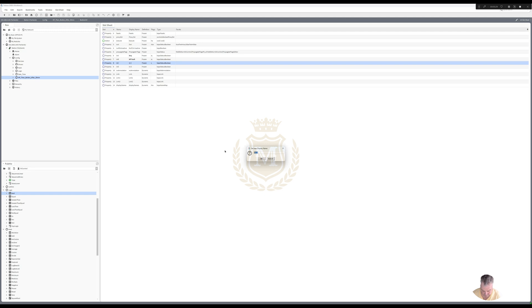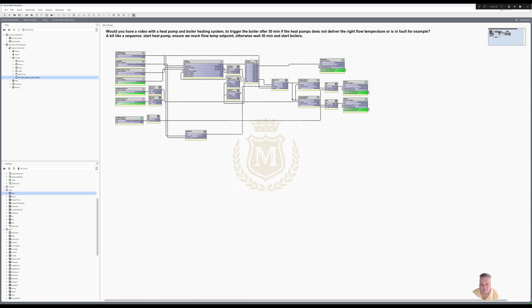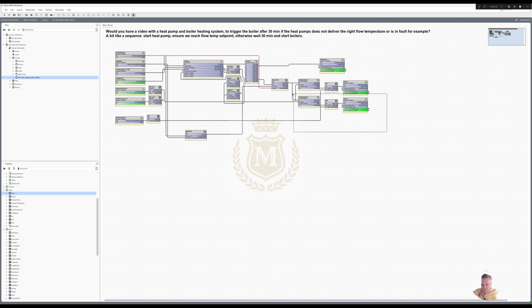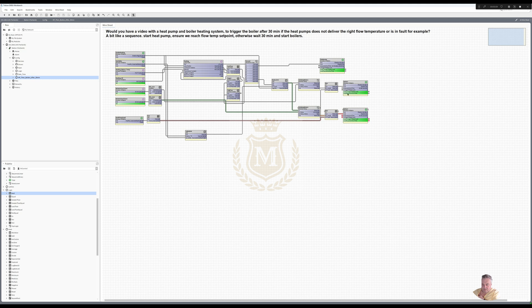So we've got the sequencer, we've got the fault which is the heat pump fault, and heating enabled. Again, that doesn't really need to be there because the sequencer would never get to a true value since this loop will be off if the heating time clock is not on — but it's just an extra bit. And if the boilers have got power — numeric power, boiler one — it's going to be 0 to 10 volts, bear in mind.